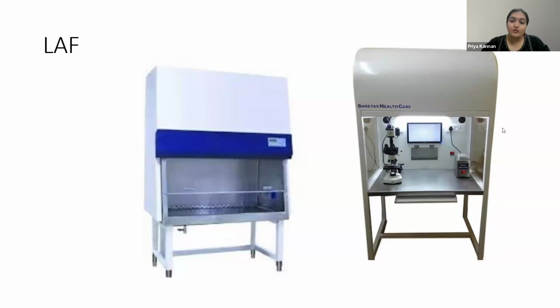Then the laminar airflow. You can have a laminar airflow, as shown here. On the left one, the blue one, you've got the filter. You've got that screen here, which is actually ideal for sperm and semen analysis, because semen is an infected sample. When the air is blowing from the laminar airflow into the face of the observer, the infected material from the semen can be pushed onto the face of the observer, and hence this is ideal for a semen analysis. However, the one shown on the right, with the microscope and the test tube warmer and the imaging system, is the most commonly used, but a small laminar airflow is good to have, though not mandated.